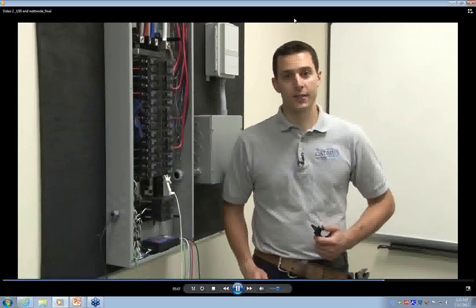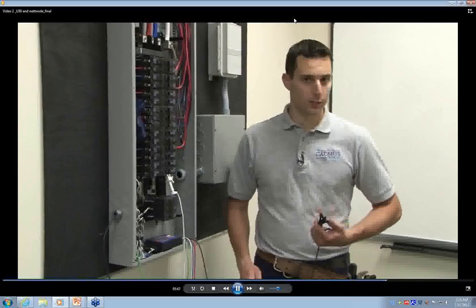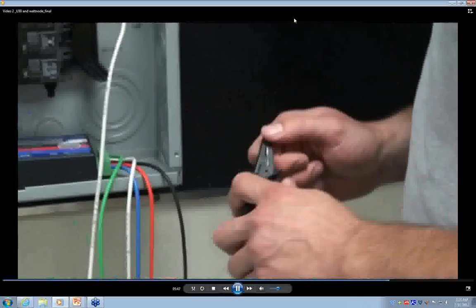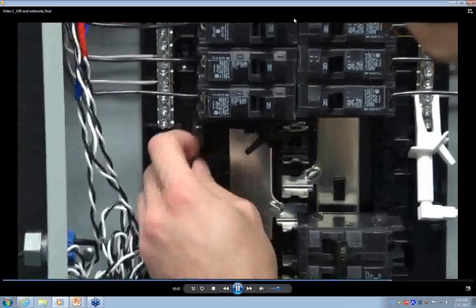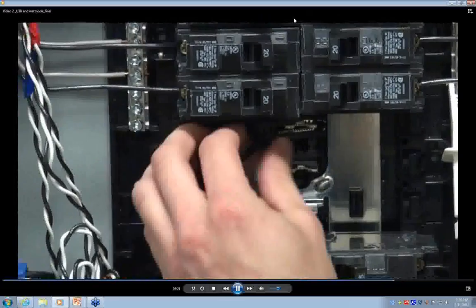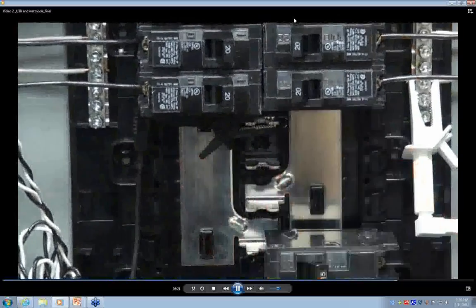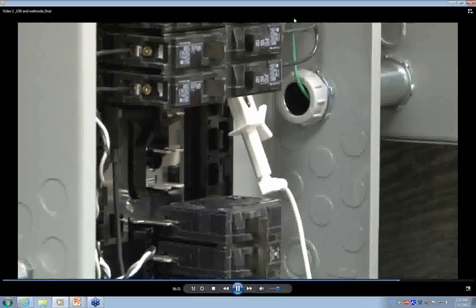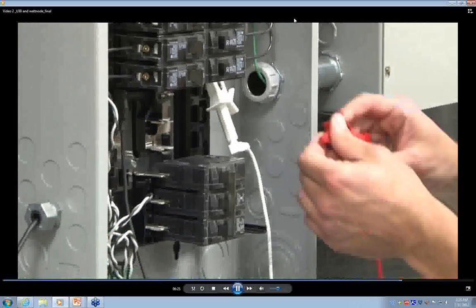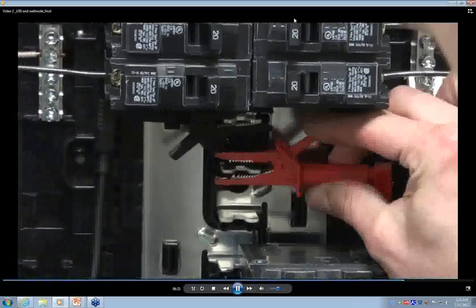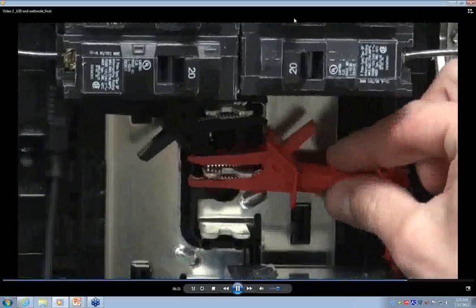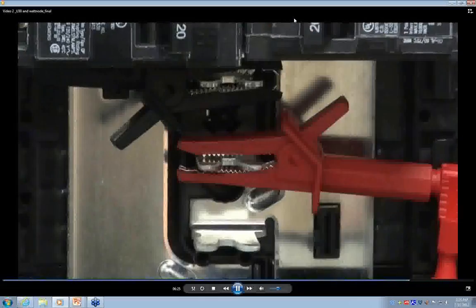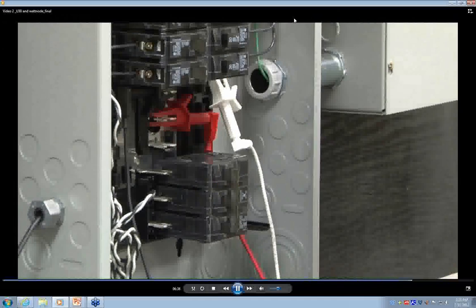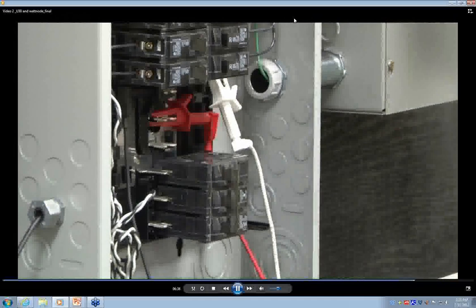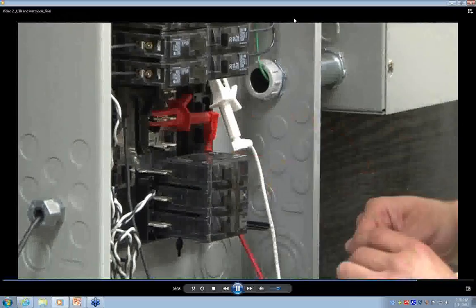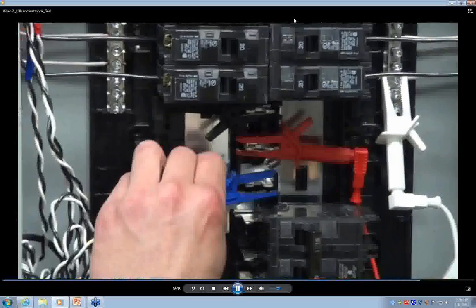Our next connection will be our phase conductors. These are the most dangerous connections we'll be making. For this, we'll connect our black phase A right over here. And once again, it's very important that the connection is solid and also not touching any other metal. We'll do the same with the red phase B conductor. We'll test our connection, make sure it's solid, and ensure that it's not touching any other phases. And finally, our blue phase C conductor will go to this bus bar right here, which is connected to phase C.